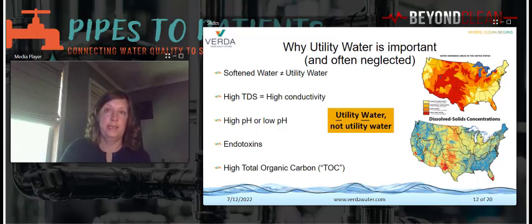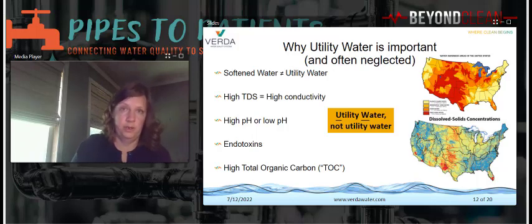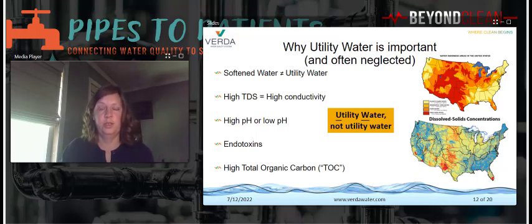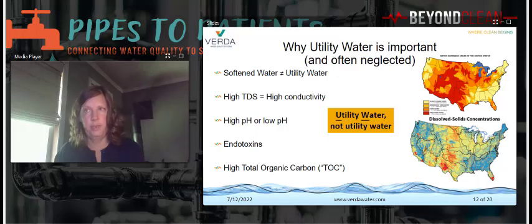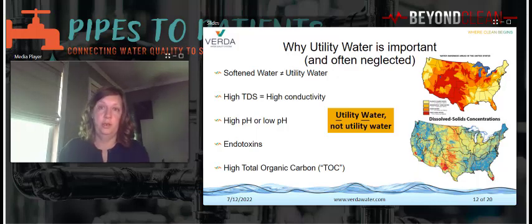Consequently, when we at MMIC talk about utility water, we're using the capital word Utility to indicate that it's a proper noun. This is intentional to indicate that water is treated and conditioned to meet AAMI TIR 34 requirements for SPD reprocessing for utility water. It's not necessarily the same as facility water. If you refer to utility water with the lowercase, it's not a proper noun. People may assume incorrectly that it's the same water that's coming right out of the tap, and that may not be the case.